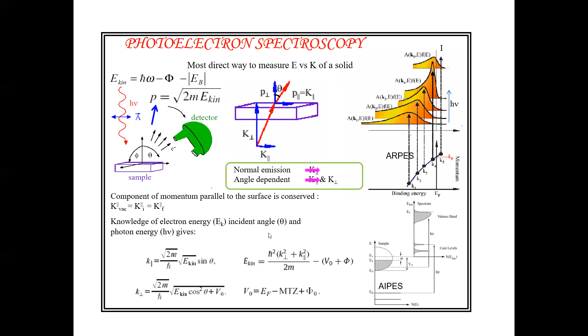This is the facility at the Indus-1 beamline, and as I already mentioned, this is the information we get. The overall resolution, in terms of millielectron volts, is 140, so we can get the information near the Fermi edge, and the vacuum available is 5 × 10^-11 millibar. Recently we have added an in situ Nd-YAG laser based pulsed laser deposition system, which is connected to our beamline chamber. You can deposit the film in situ in this chamber, and without breaking the vacuum, using this transfer rod, transfer it to the analysis chamber for in situ characterization of the sample.